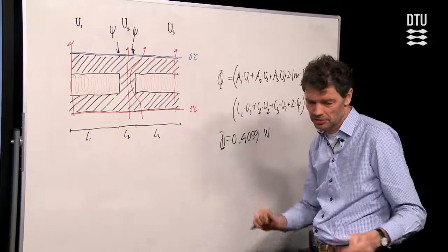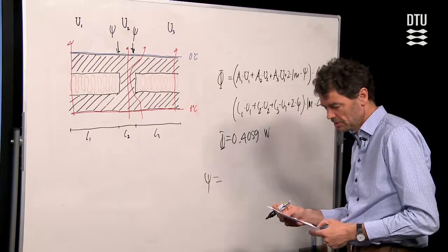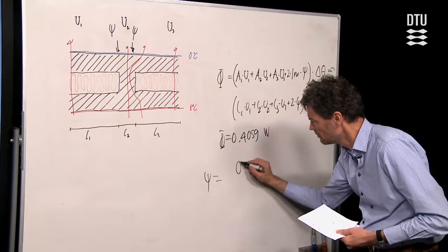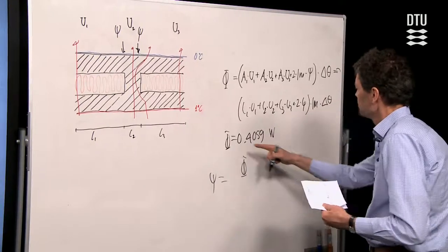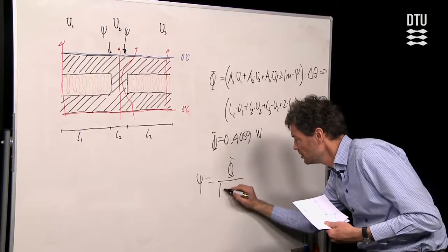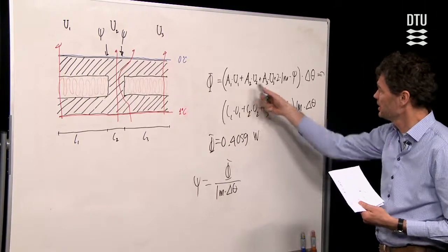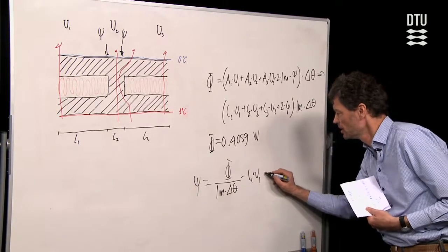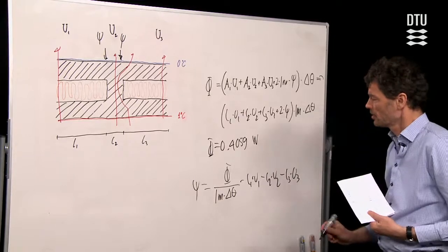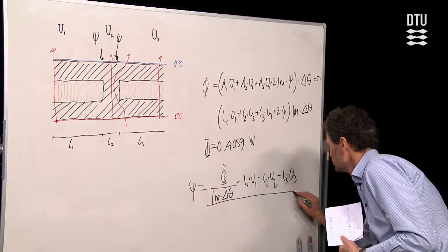So that we should then use to isolate Psi. When I do that, I have to be careful here. Then I have Psi in a calculation, which tells me that we should take phi equal to the heat flow that was calculated by the program. But if I take phi, I should divide by 1 meter, and I should divide by delta theta, the temperature difference. And then I can subtract all the things I have. I can subtract L1 times U1 minus L2 and U2 minus L3 times U3. That was almost Psi because I had two of them. So I have to divide in the end the result by 2.